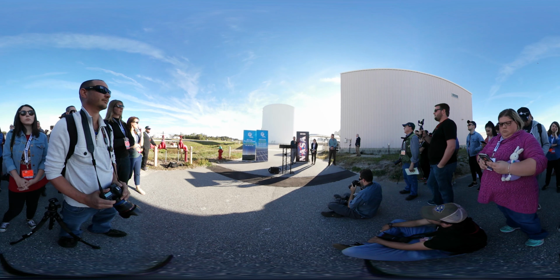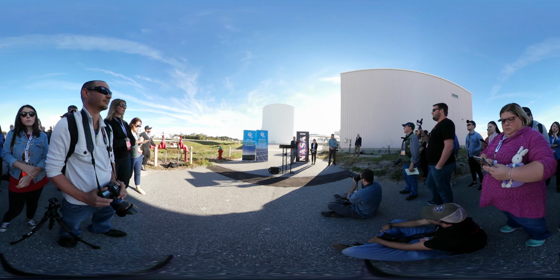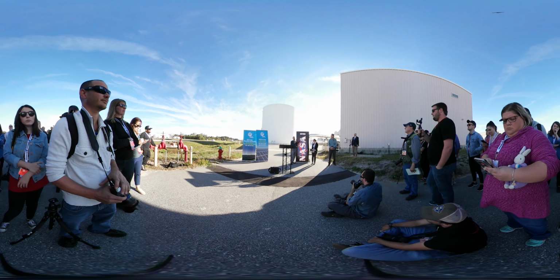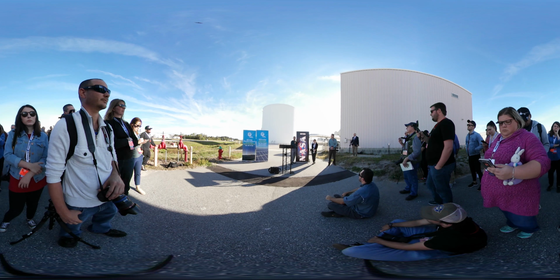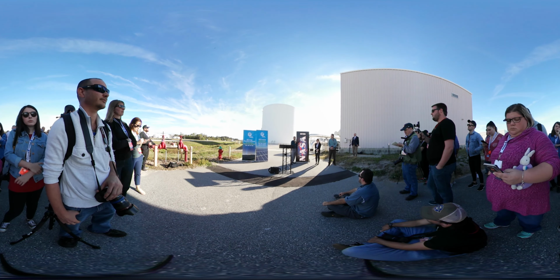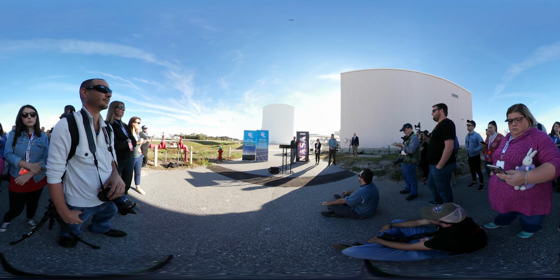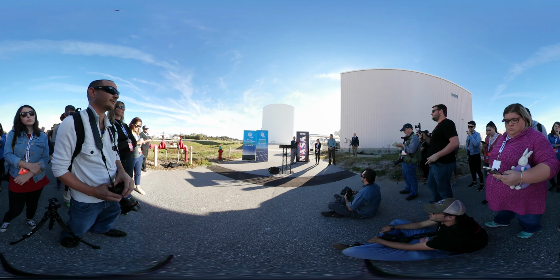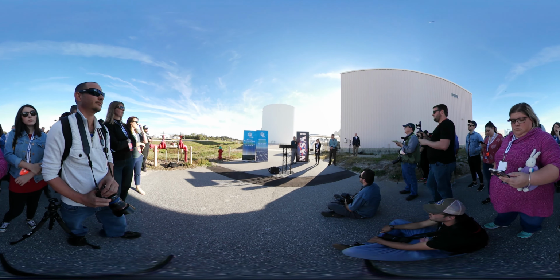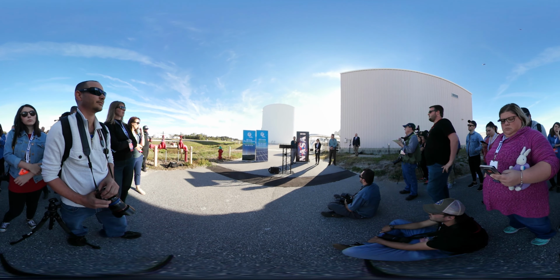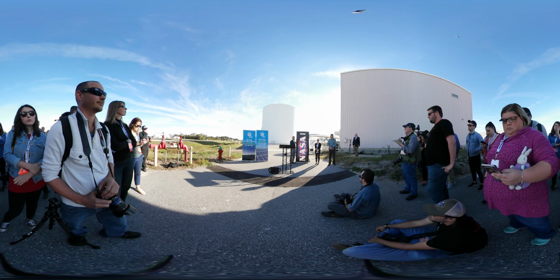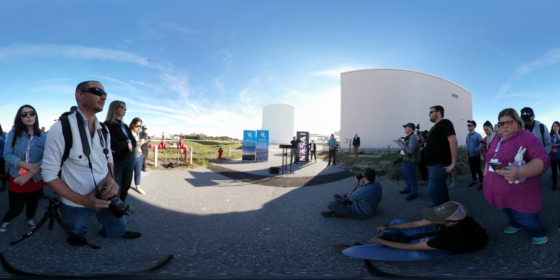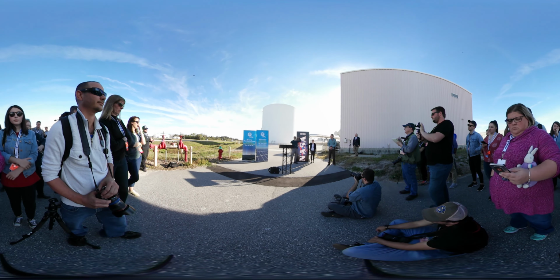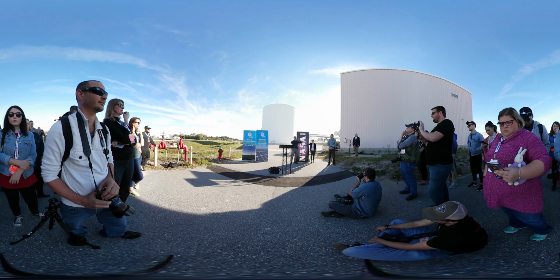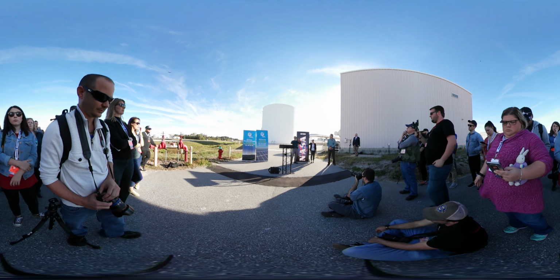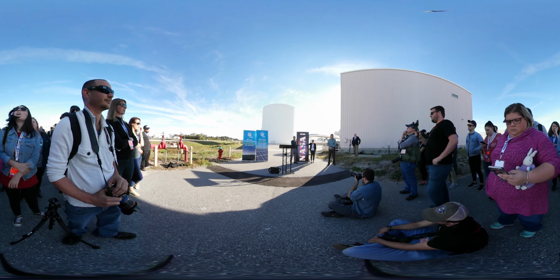The only thing that changes is the temperature of the water. As the energy is discharged, at the top you have approximately 40-degree water, then you start using it, and water is coming in at around 49 degrees at the top. It's important not to create any turbulence, so we have diffusers inside. You gently and gracefully introduce the warm water so that you maintain what's called a stratified system—meaning there's a very small area where the water changes temperature. You may have 6 inches where it goes from 40 to 49 degrees, and that's called a stratified system. We keep it that way by avoiding turbulence, with diffusers both at the bottom and at the top.